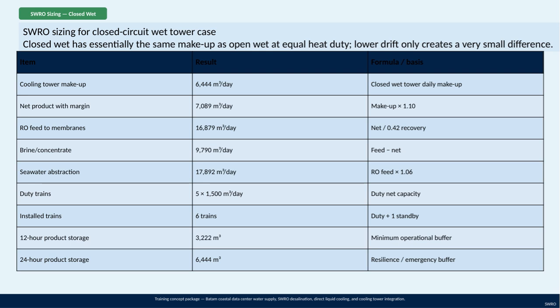For capacity planning, the system operates with 5 duty trains that each handle 1,500 cubic meters per day, totaling the net product requirement, plus 1 additional train installed as a standby for reliability. Finally, there's storage for operational resilience, 3,222 cubic meters for a 12-hour buffer, and 6,444 cubic meters for a full 24-hour emergency buffer to ensure continuous supply in case of any interruptions. This setup balances efficient water treatment with operational security for the Batam Coastal Data Center project.